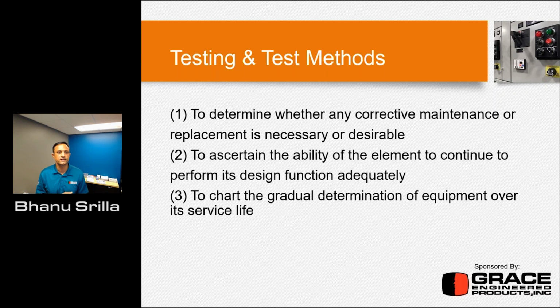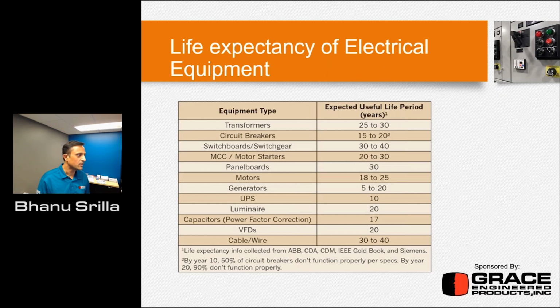ANSI NETA or NFPA 70E have definitive guidelines and tables to that effect, so just go back and look at those. The standards are available to buy from the ANSI website as well. The goal is to chart the gradual deterioration of equipment over its service life. As I mentioned before, for example with thermography, high pot testing, insulation resistance, or dielectric strength, you need to go back and look at previous records to see how they compare and what kind of trend they show, so that you can take the appropriate corrective action, okay?